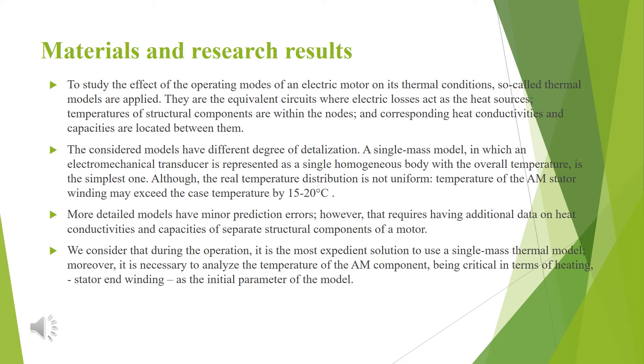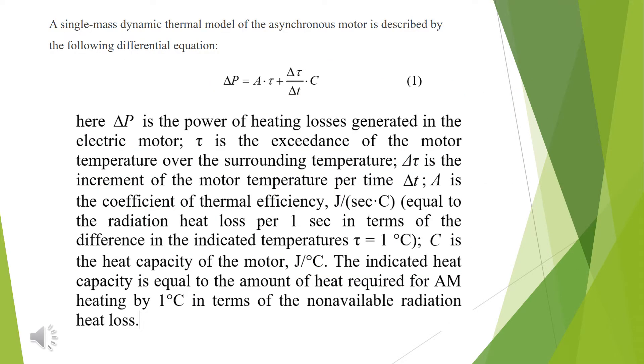We consider that during operation it is most expedient to use a single-mass thermal model. Moreover, it is necessary to analyze the temperature of the asynchronous motor component critical in terms of heating — the stator winding — as the initial parameter of the model. A single-mass dynamic thermal model of an asynchronous motor is described by the following differential equation, components of which are shown below.